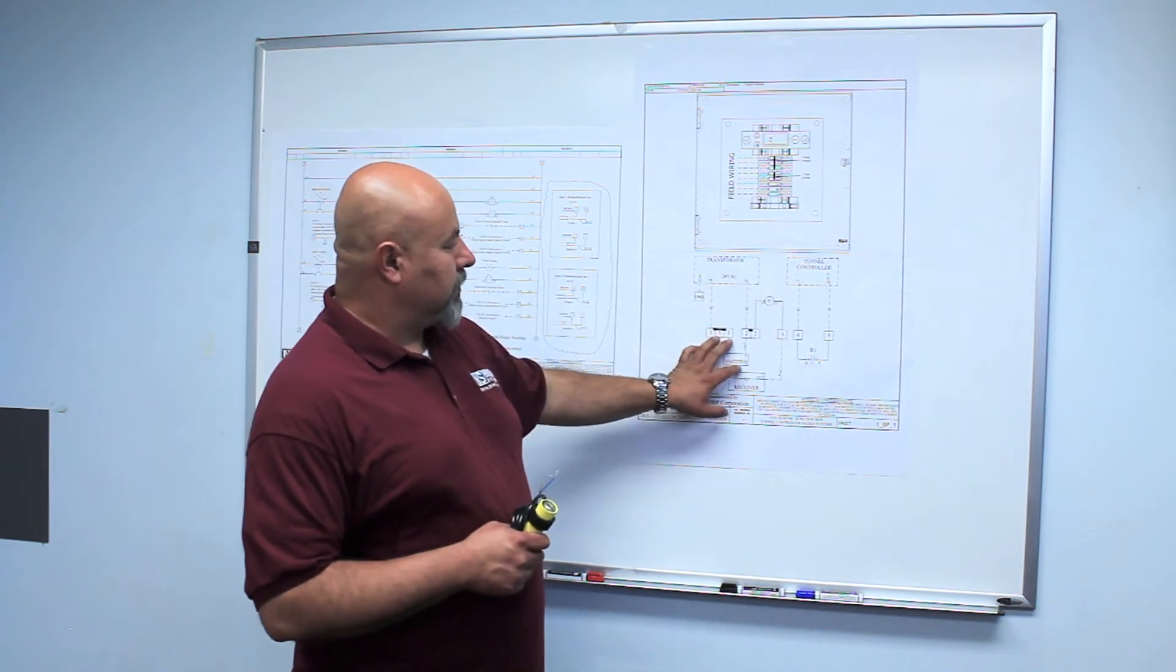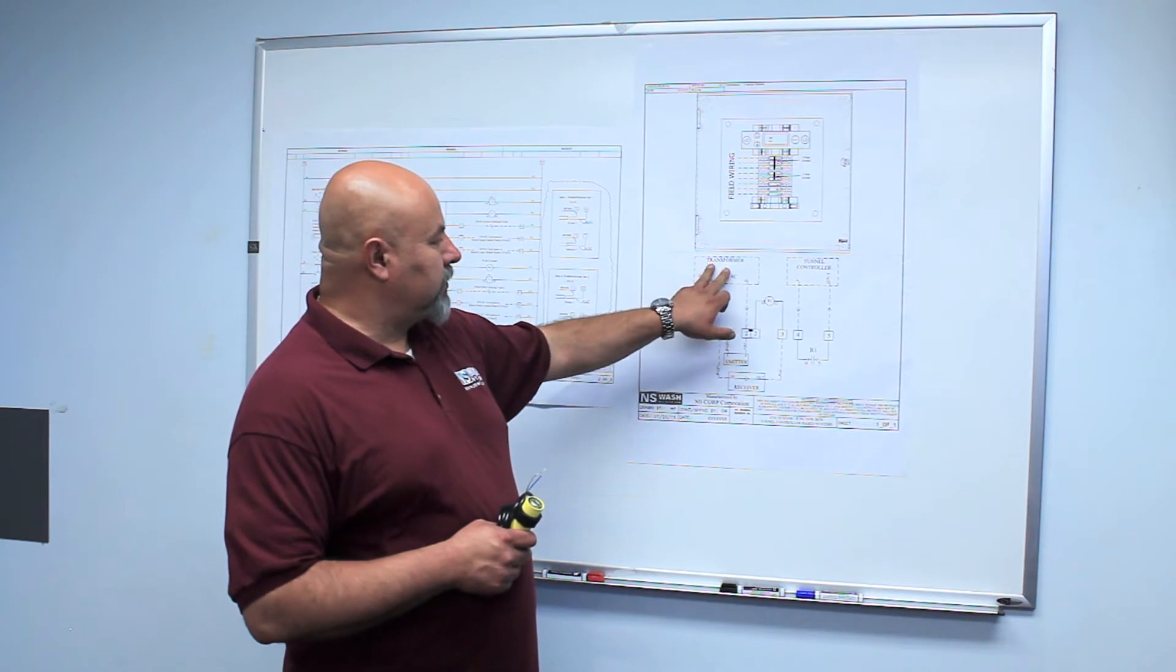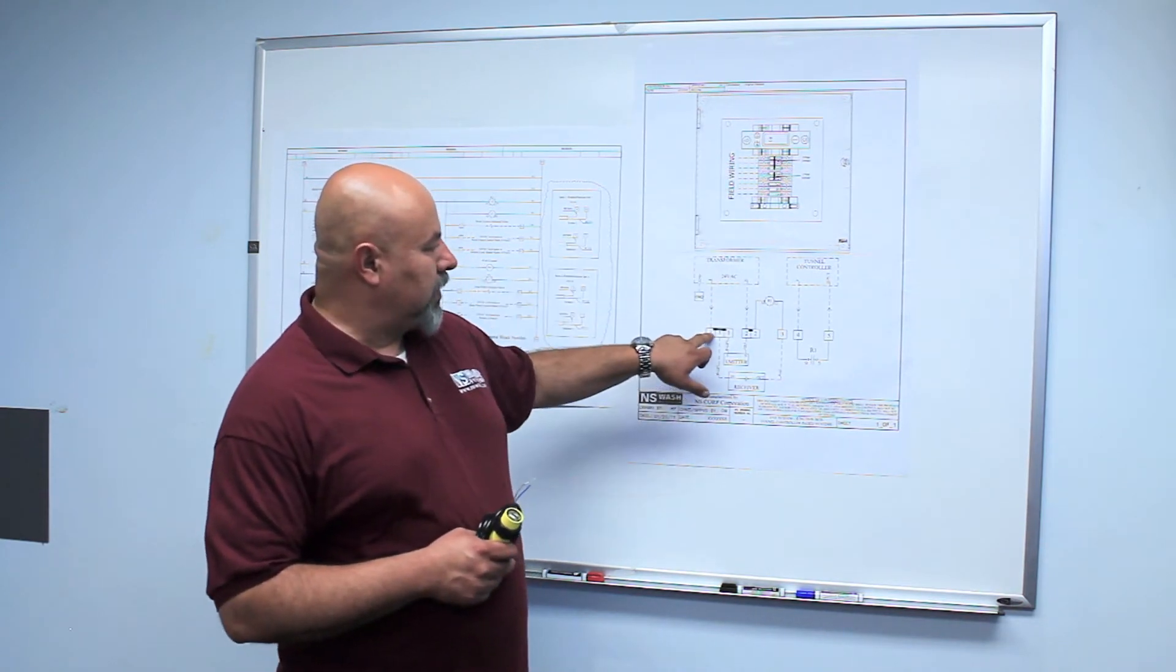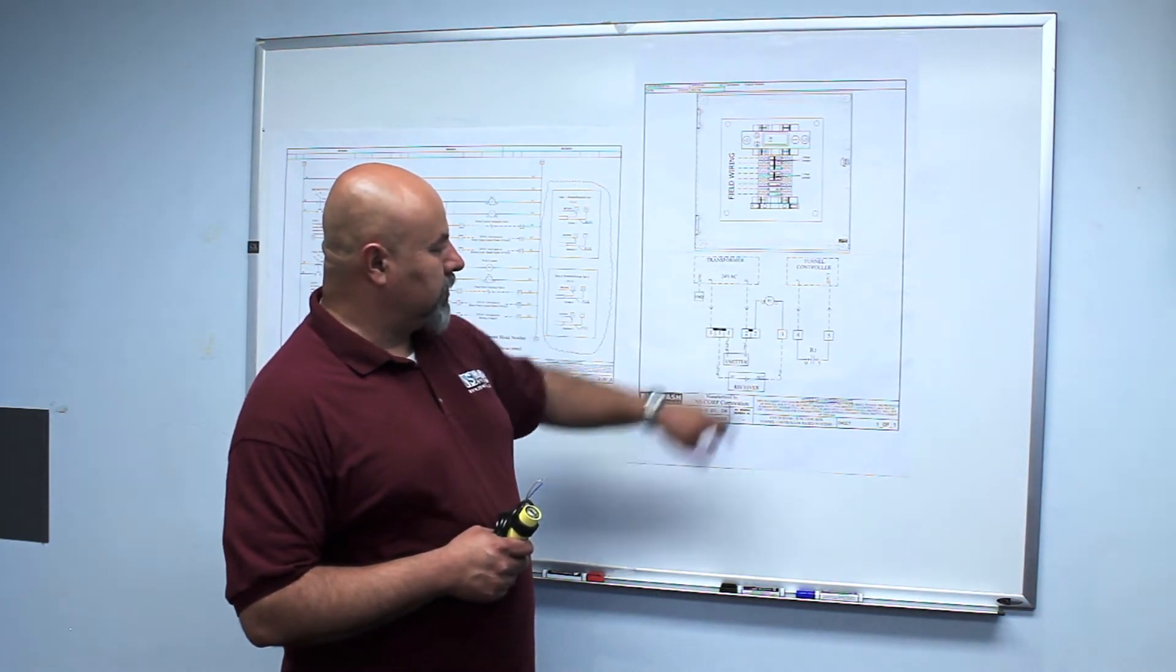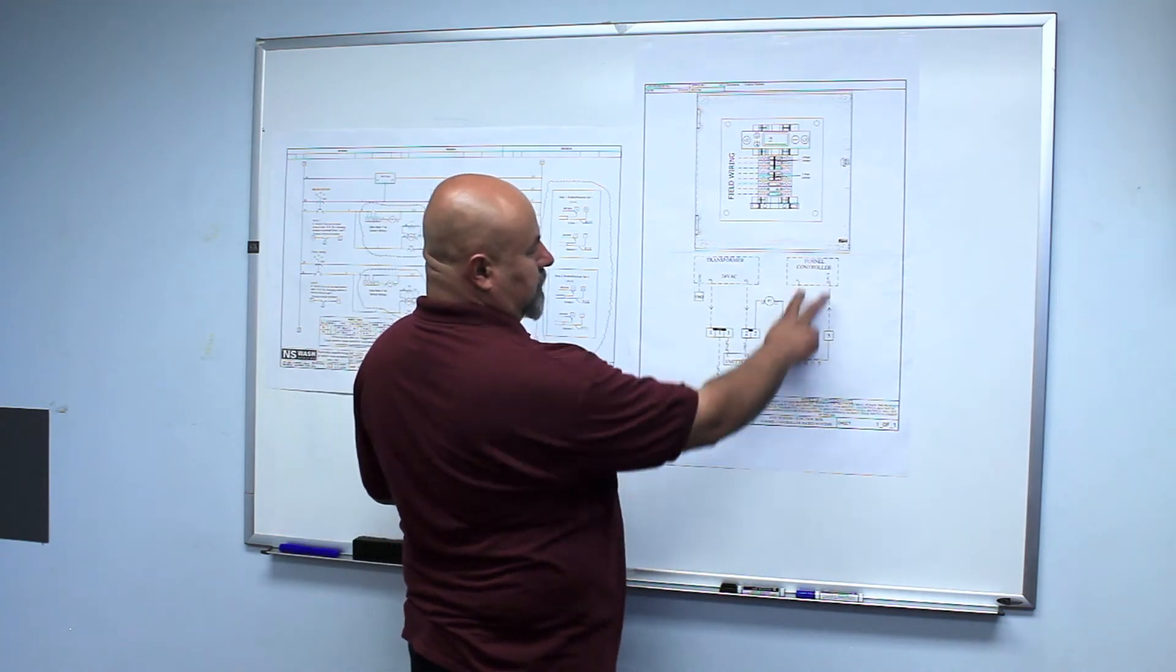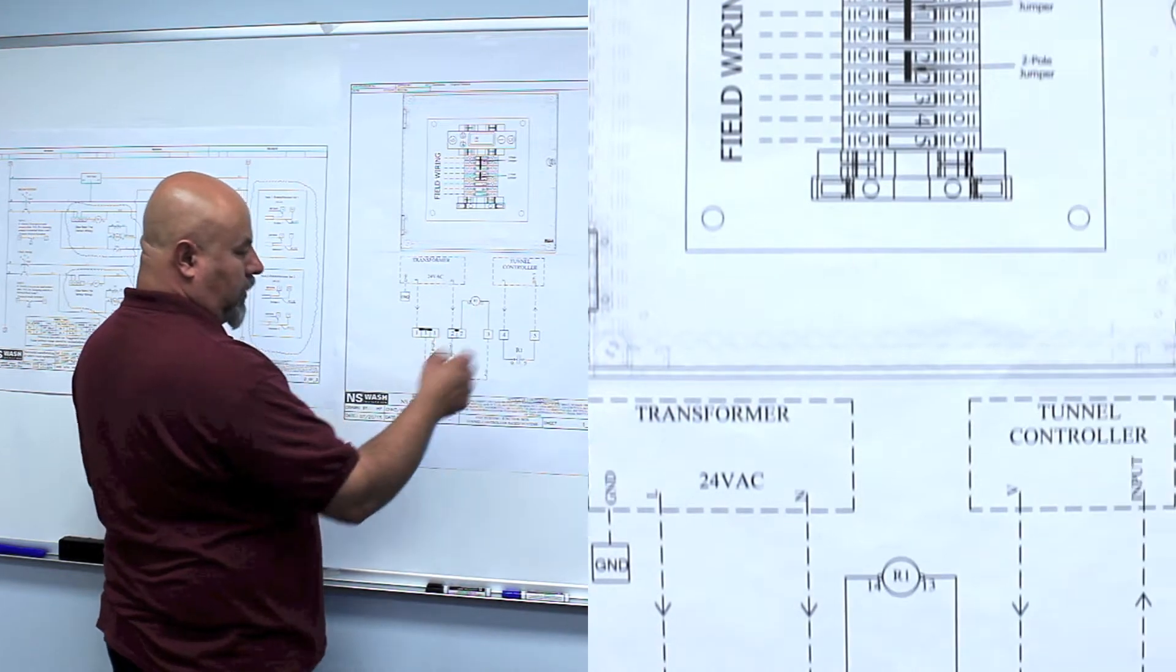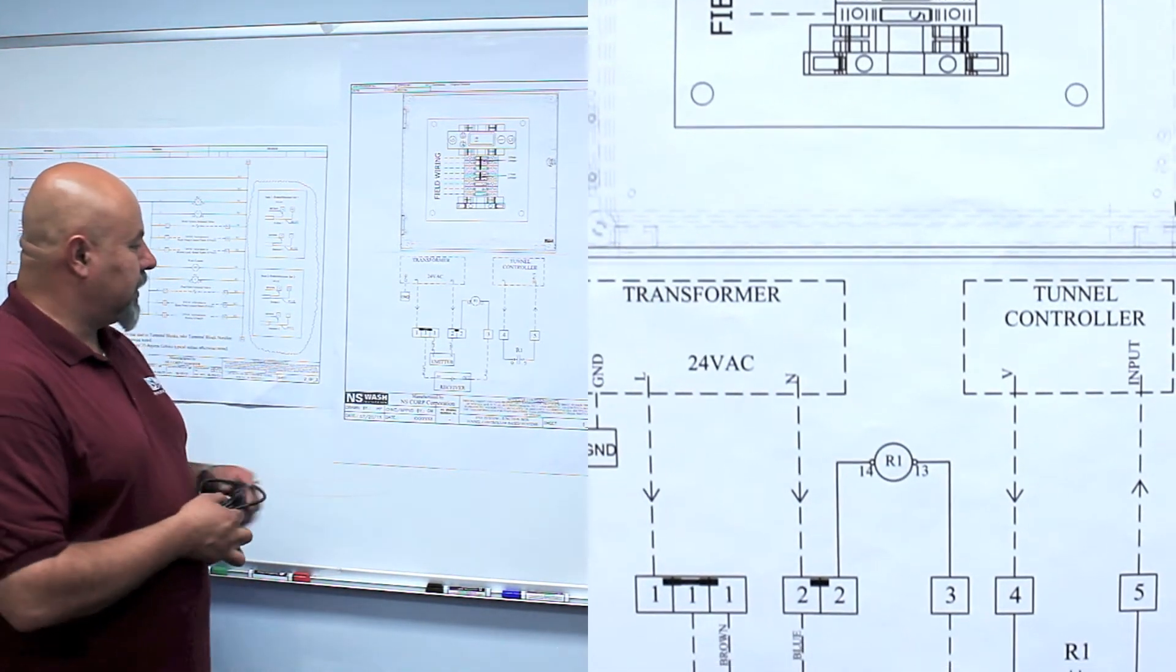Here's how this wiring connects. You have to bring in from your transformer 24 volts to this panel, which is wired to number one, the load side of the panel, the neutral side of the panel to number two. The output of this would be to your tunnel controller out of R1, relay one. Now, here's how the photo eyes connect in here.